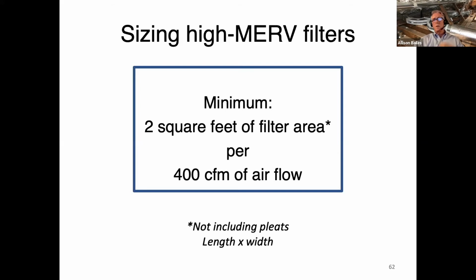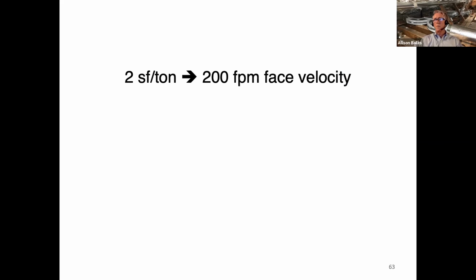And that gets us a low pressure drop across the filter. If you're wondering about face velocity, some of you more technical people out there, 2 square feet per ton is about 200 feet per minute of face velocity. And filters are usually tested at about 500 feet per minute of face velocity. Lower velocity through the filter usually means better filtration as well.